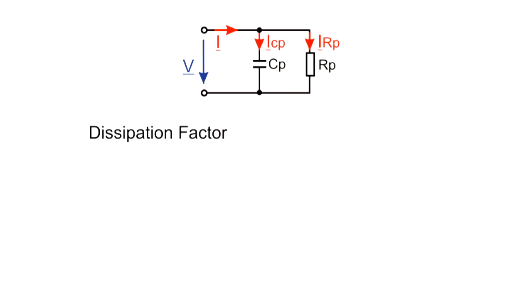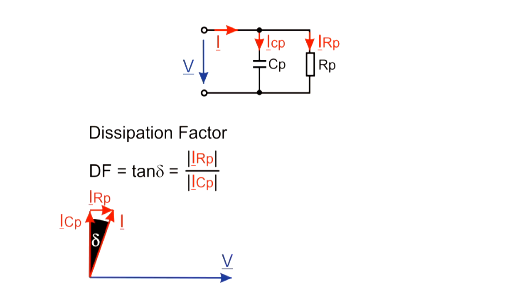As a result of the losses in a real system, represented by the resistor in the equivalent circuit, the phase angle differs from 90 degrees by the angle delta. The dissipation factor is defined as the tangent of this angle delta, hence its alternative name, tangent delta.